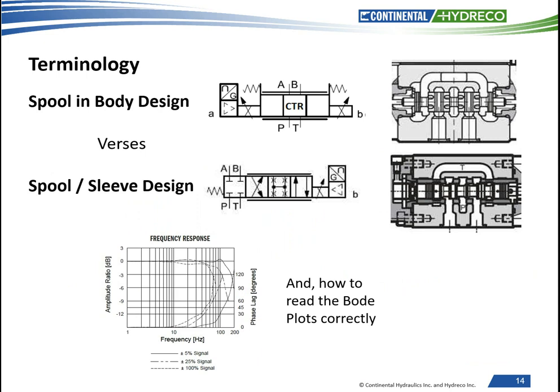Okay, throughout this introduction, I've referenced a couple of different designs. The first one is the spool in body, which is just that: a production-made spool in a production-made body. Although spools are made today with high precision, there is still some tolerance variance between one batch of spools to the next. Production-made bodies also have tolerance variances due to small internal core shifts. Standard valves also use centering springs and centering washers that could also have some variations.